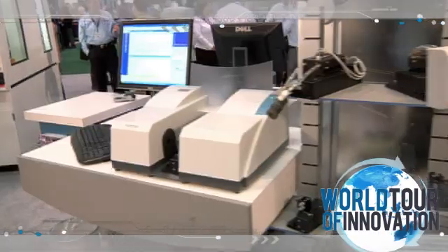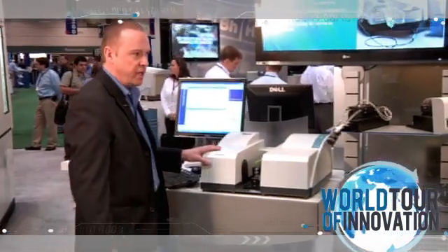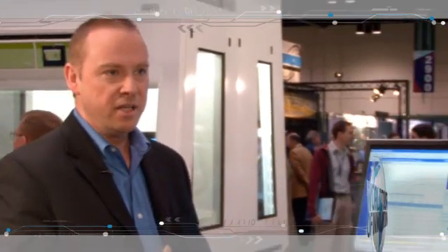The first product we're showcasing is the new Evolution Array. This is a photodiode array based UV-Vis spectrometer. The advantage of a photodiode array is that it enables you to acquire the entire spectrum in a single second, unlike traditional UV-Vis spectrometers which acquire the spectra in a sequence of wavelengths — this acquires all wavelengths simultaneously.